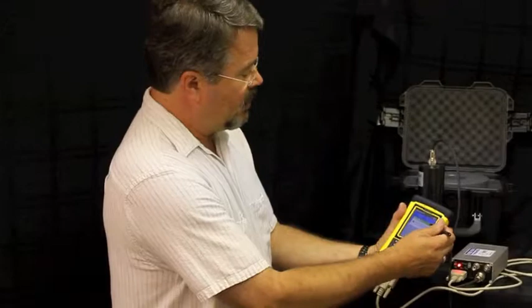Now the process itself can be pulled up from any of these menus. We can do auto gain stabilization, and the first thing that it will look for is to make sure that we are using a known substance with a known energy and a known weight. This is potassium chloride filled in here. Of course, with any potassium chloride, there's always going to be a certain population of potassium-40, which is a naturally occurring radioactive material. It has a very characteristic energy at 1461 keV, kiloelectron volts.